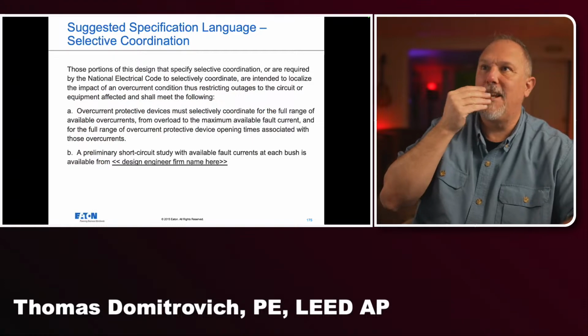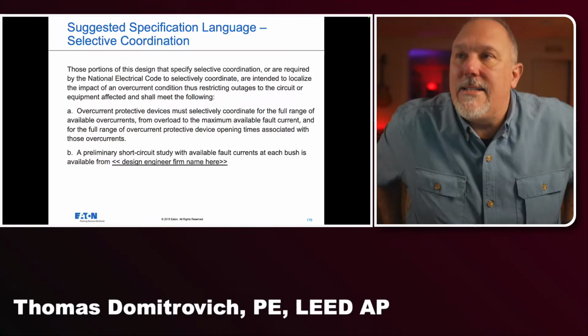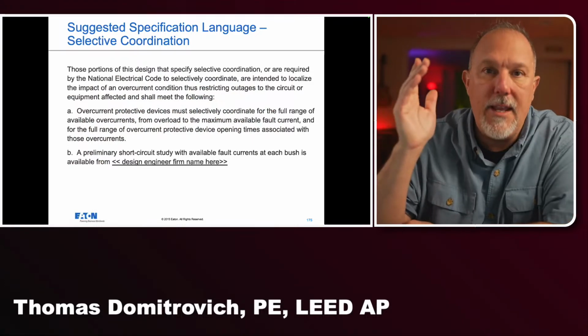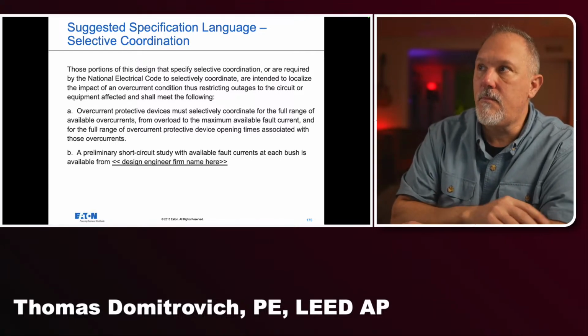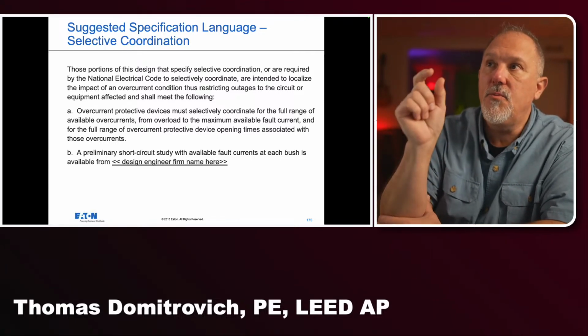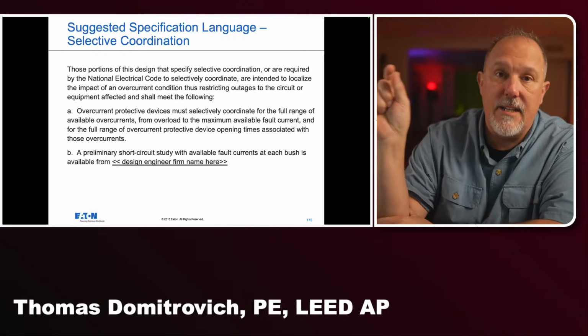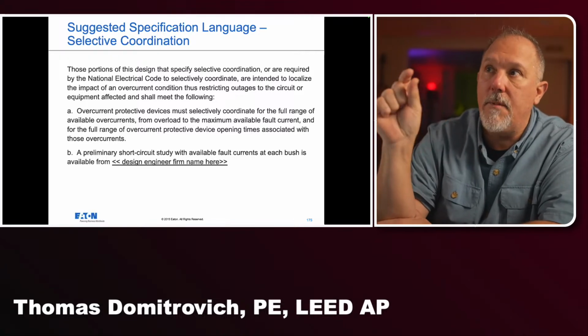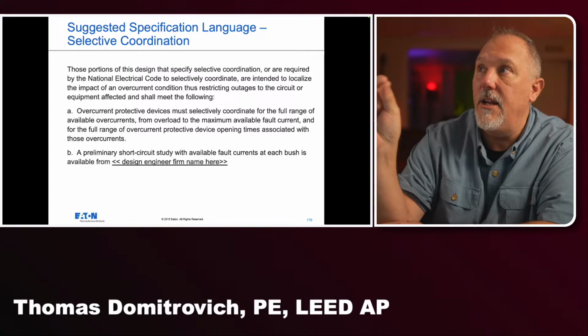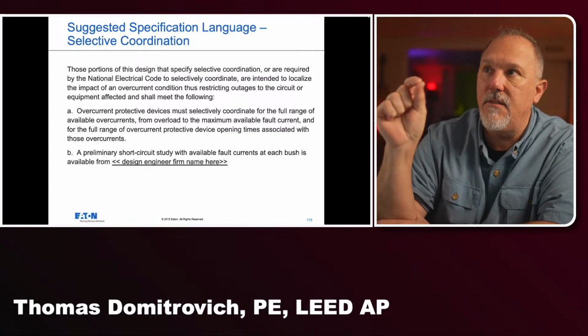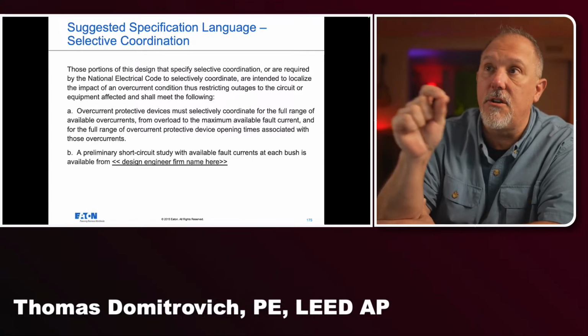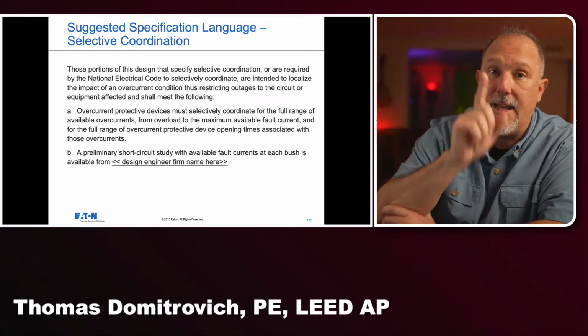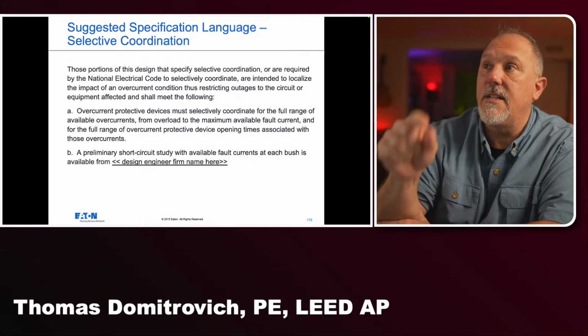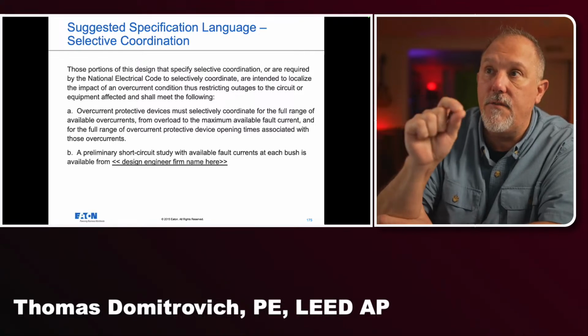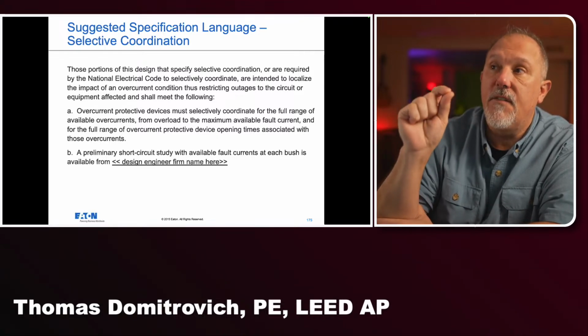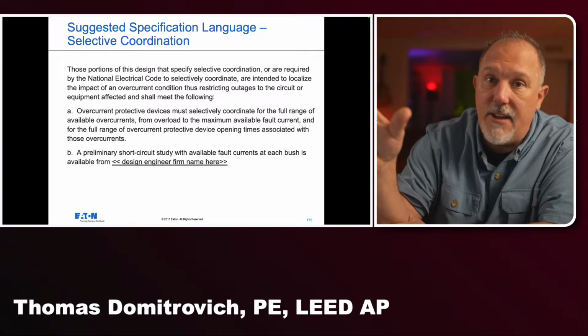So what I suggested was language in the specification to be clear. Those portions of the design that specify selective coordination, or are required by the National Electrical Code to selectively coordinate, are intended to localize the impact of overcurrent conditions, thus restricting outages to the circuit or equipment affected, and shall meet the following. A. Overcurrent protective devices must selectively coordinate for the full range of available fault overcurrents, from overload to the maximum. That's right out of the definition.